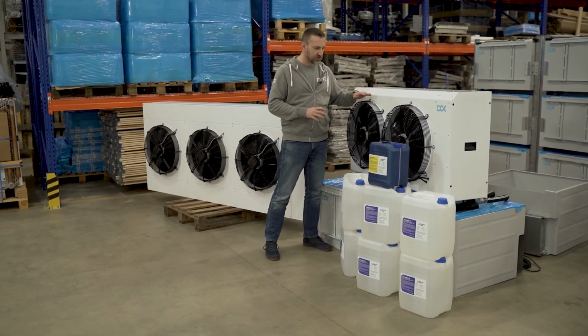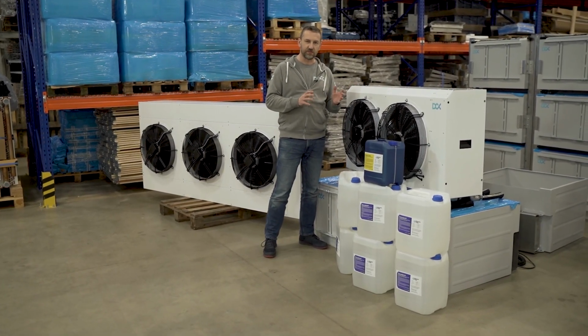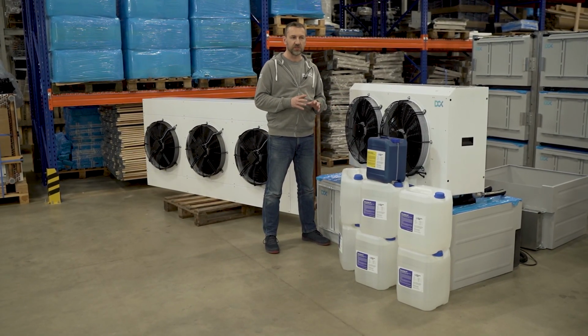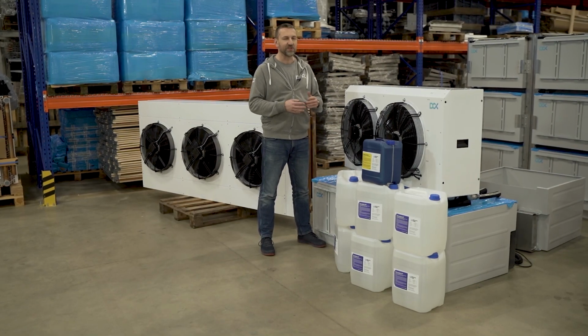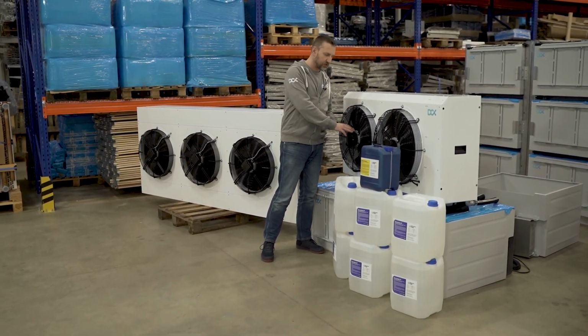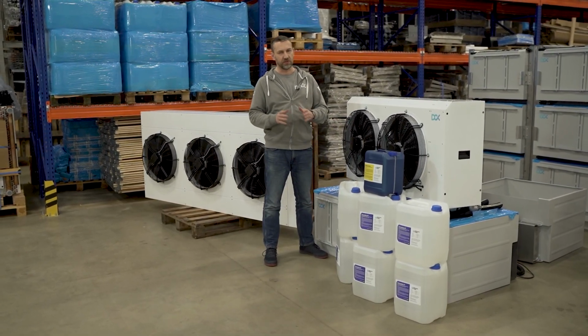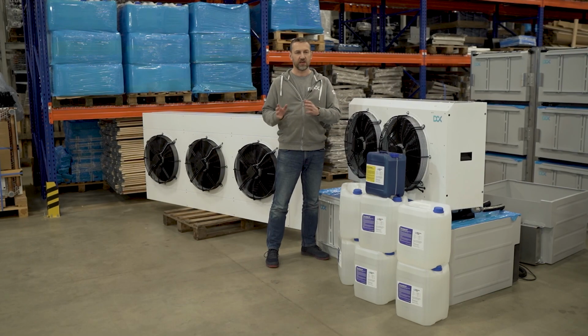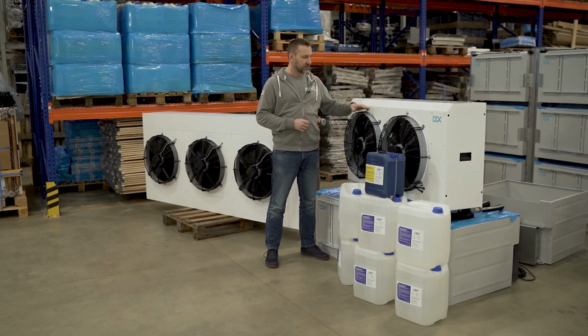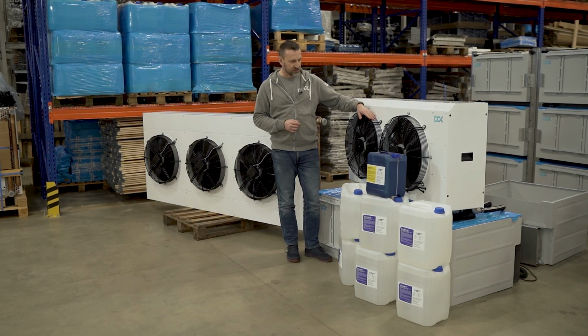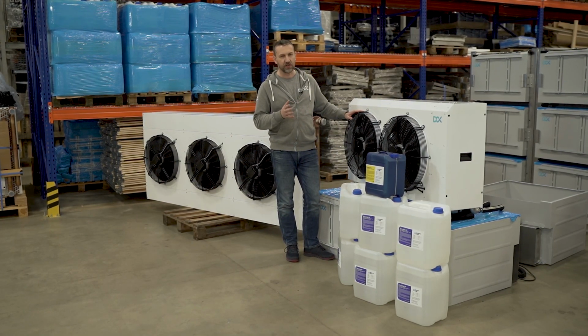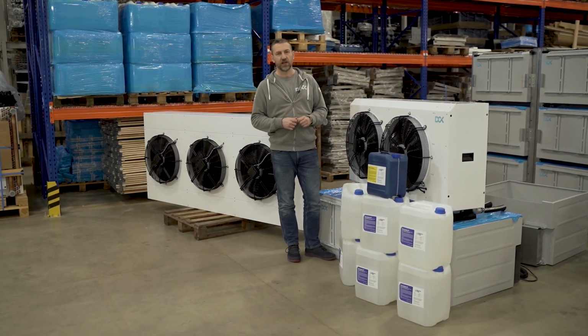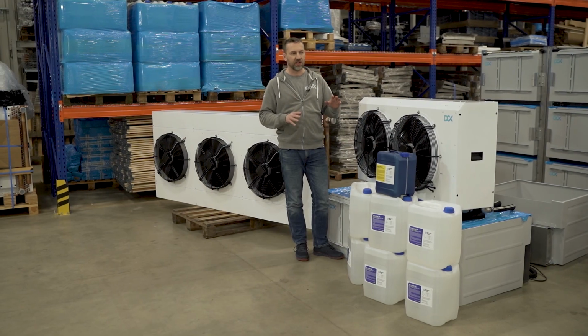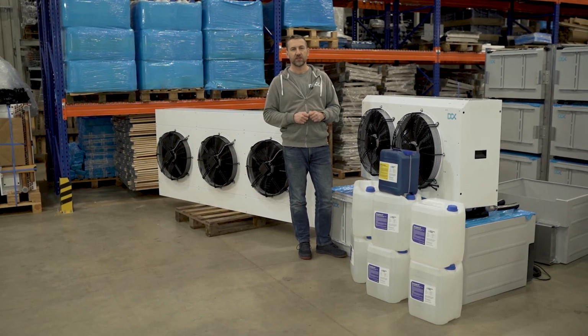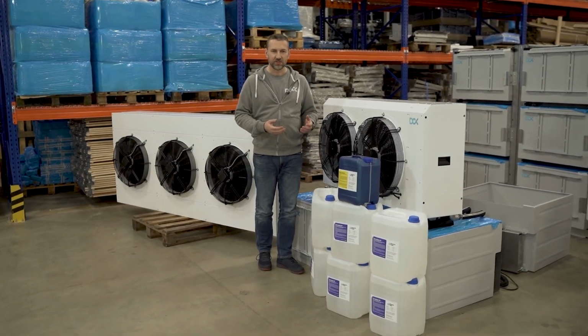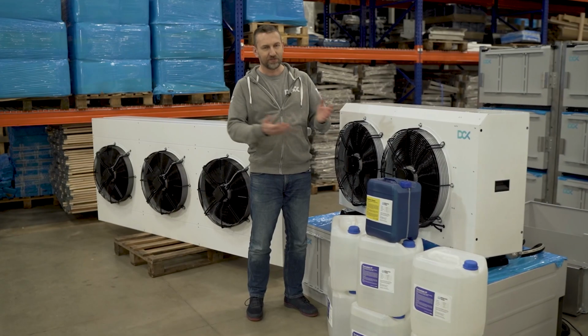And we're using 2 fans. Each of those fans takes approximately 350, depending on the model, because we are using different fan models, whichever is available. So we are using for sure 50 and 60 hertz fans, so they work both in the US or in Europe or in Asia or in Australia for that matter. Those 2 fans take approximately 320-350 watts each. The pump takes 180 watts. So altogether we are in the area of 1 kilowatt more or less of power, and that's all you need to spend power-wise for the 40 kilowatt of heat rejection.